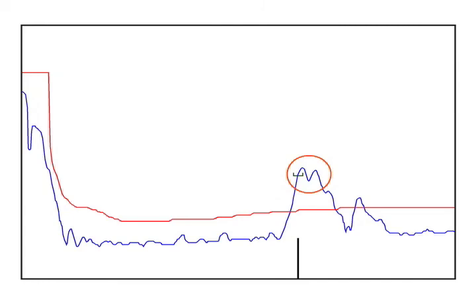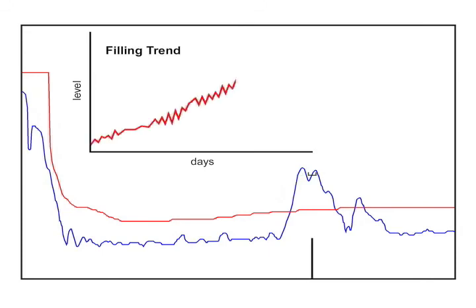This monster creates problems when the sensor is trying to select the correct echo. Sometimes it will pick the first echo. Sometimes it will select the second echo. If you were to look at these echoes over time, say for example on a filling trend graph, you would see something like this. Your customer would be asking, If we fill the vessel at a constant rate, why do we see such an ugly trend and how do we fix it?